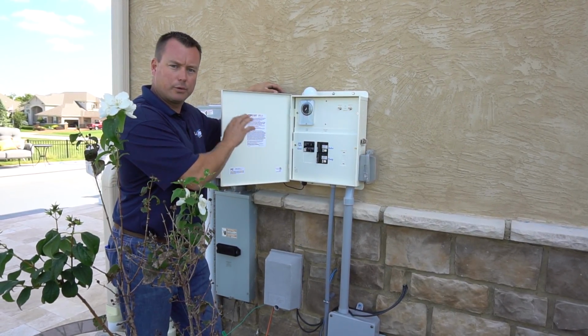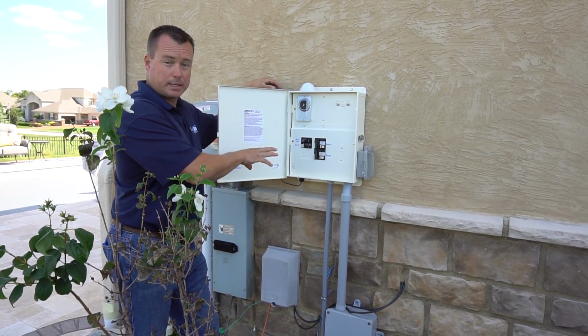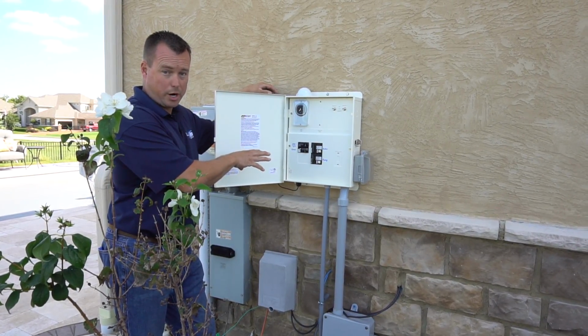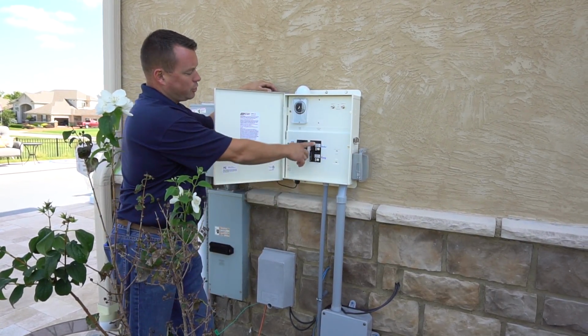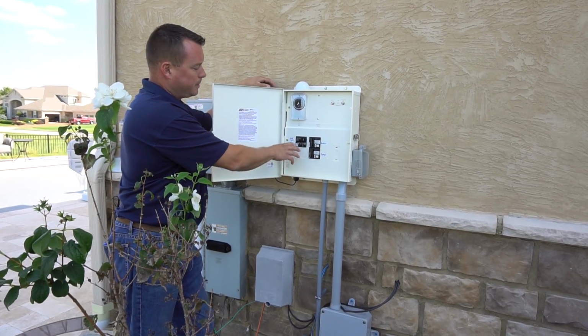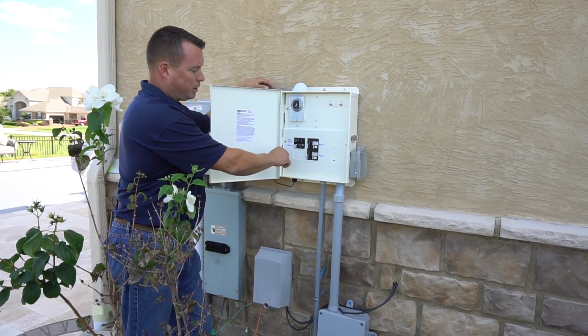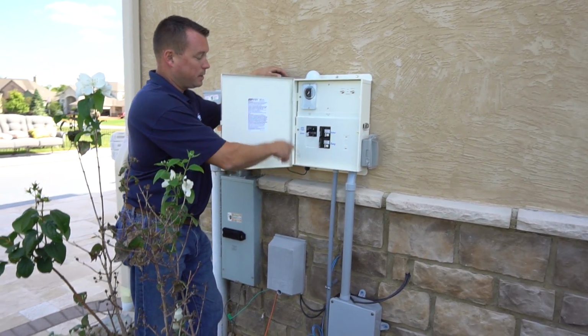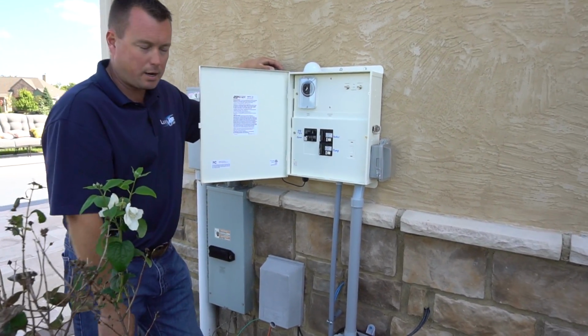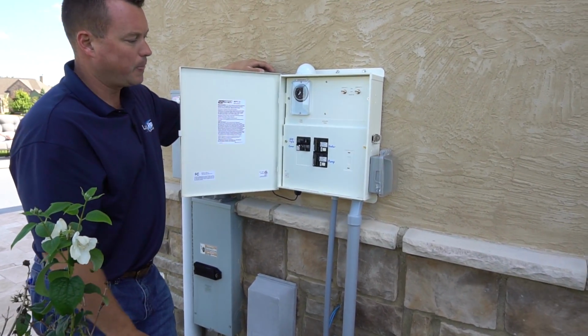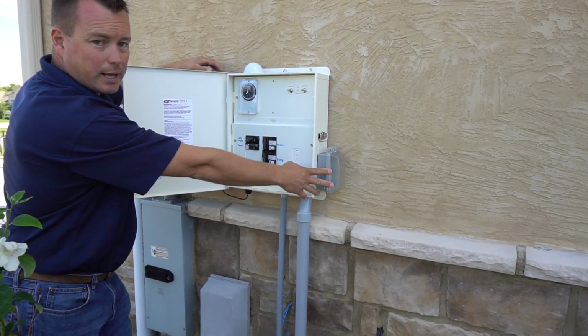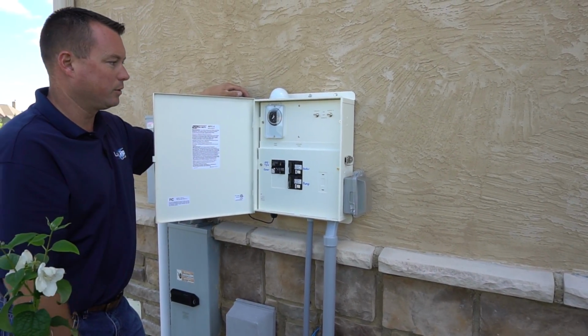On all of our pools, we install a designated 100 amp or greater panel. We've got our circuit breakers in here for each component. Heater, we've got our pump, our GFI and lights, and then this particular installation has an automatic cover, and that circuit breaker is here. We also have a GFI outlet on the side of the panel as well.